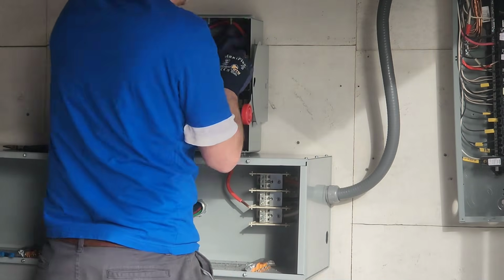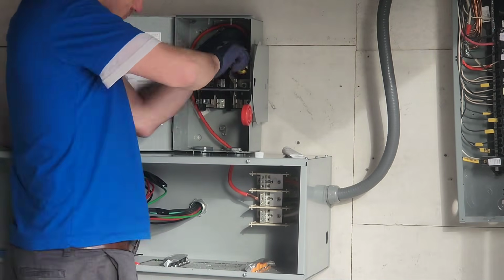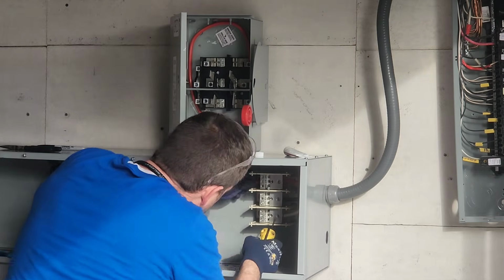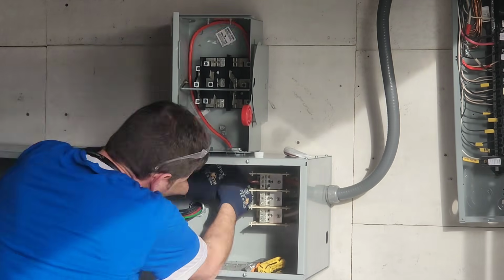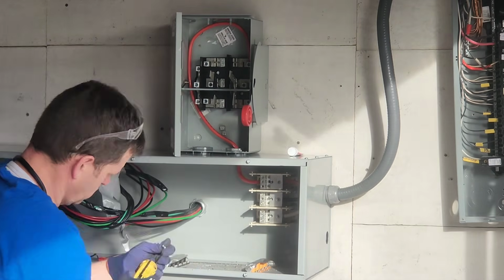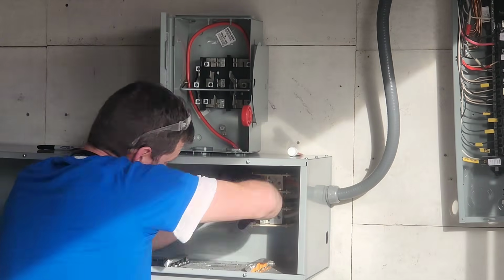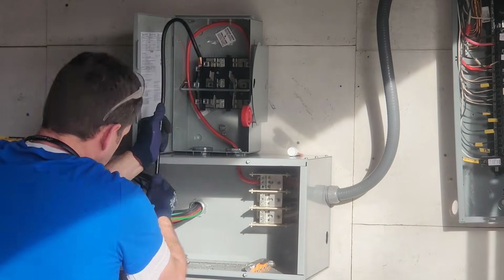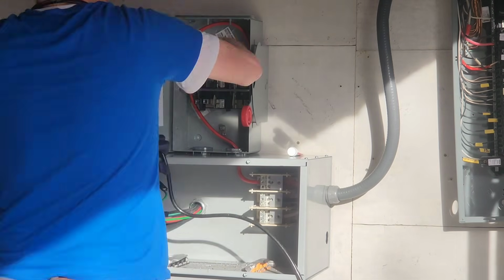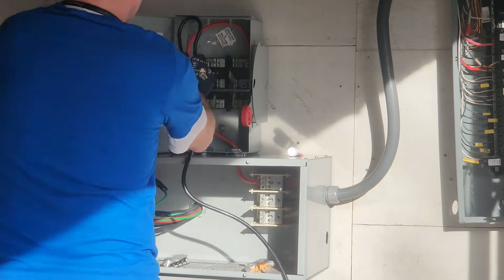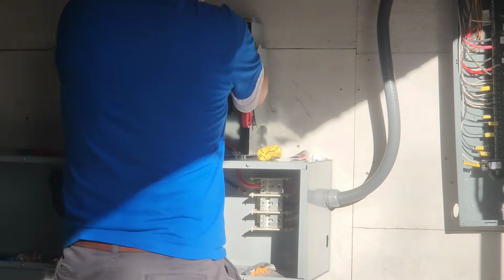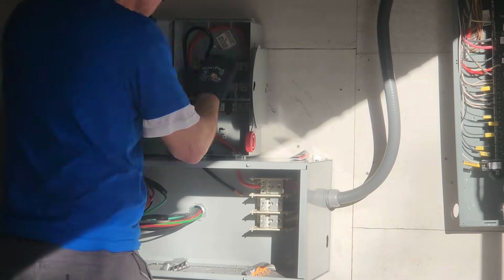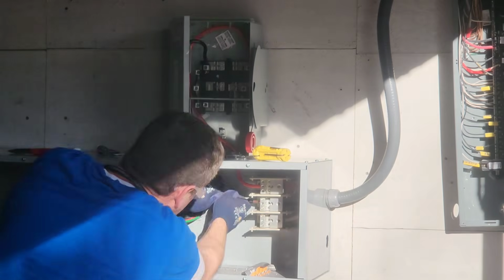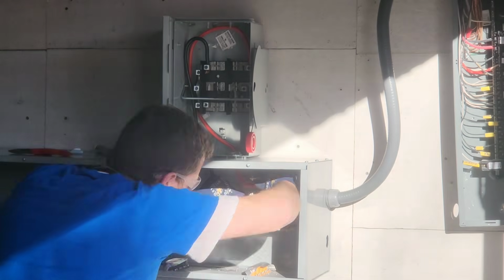Next I'm going to be extending the grid conductors over onto the transfer switch. The grid terminals are going to land on the top lugs of this transfer switch. I could put them on the bottom, but I decided to put them on the top because that's where I had my sticker - so if my switch is in the up position, I will be on grid.